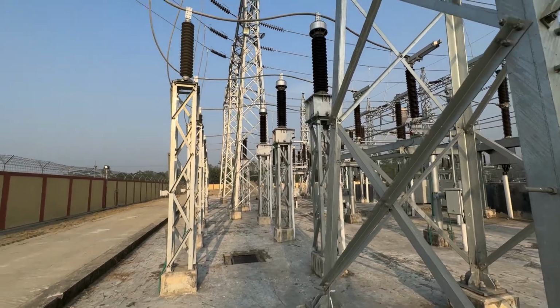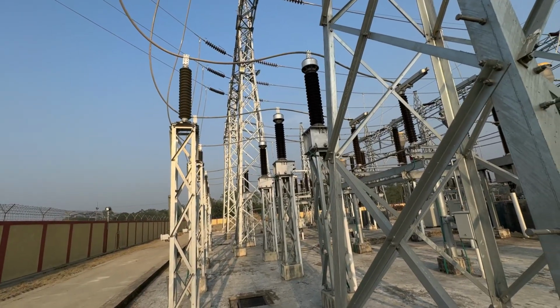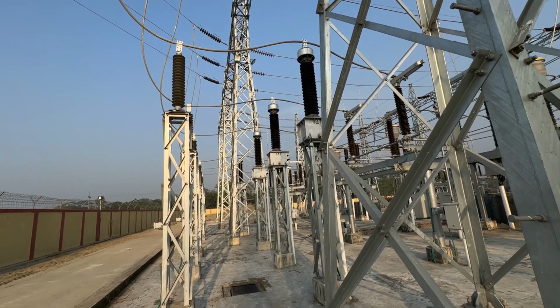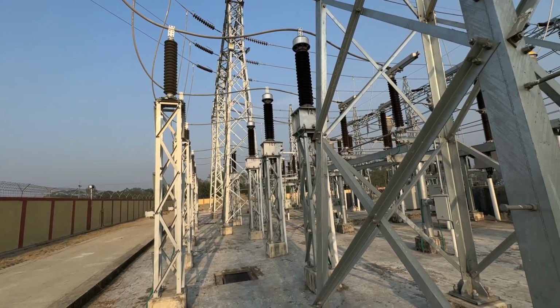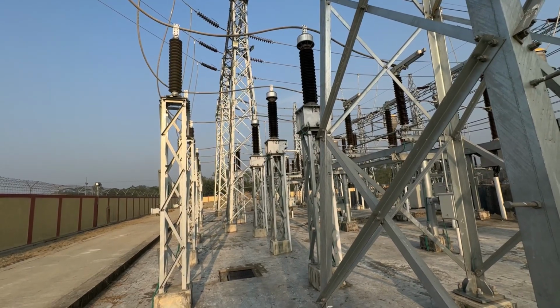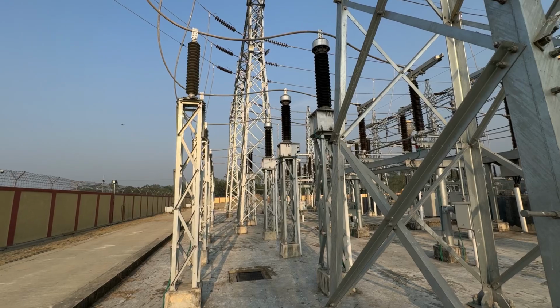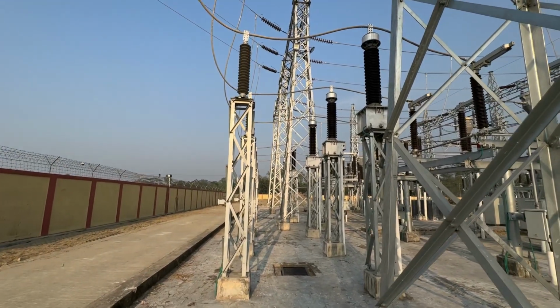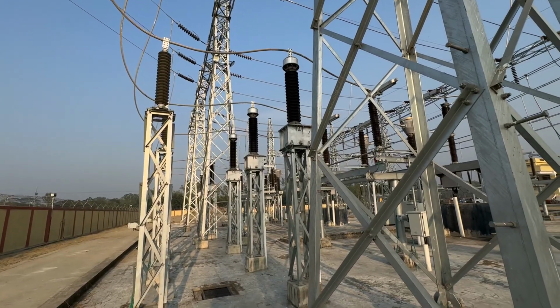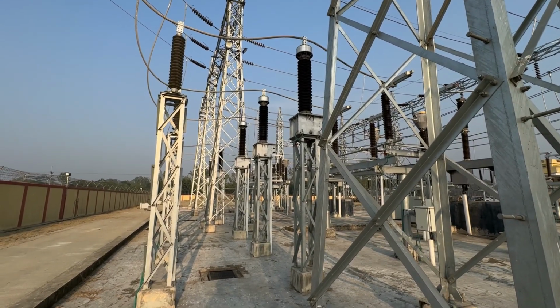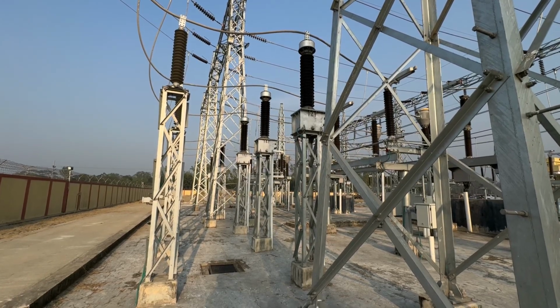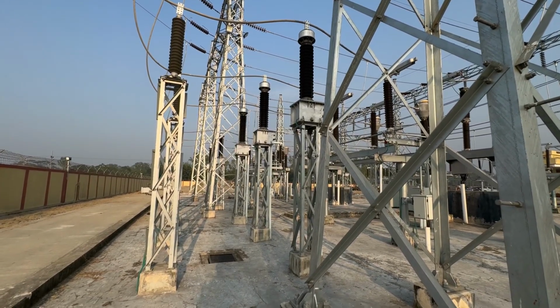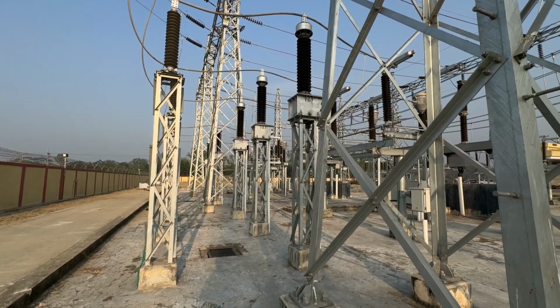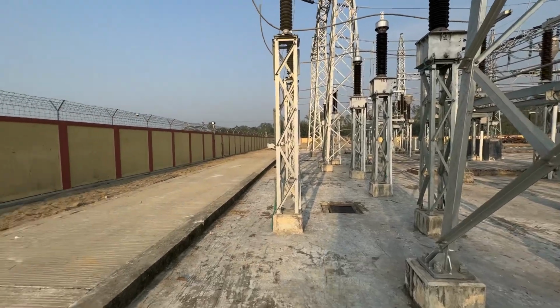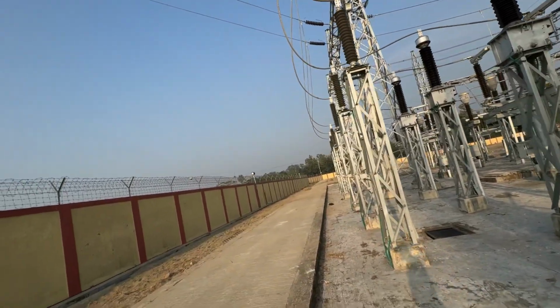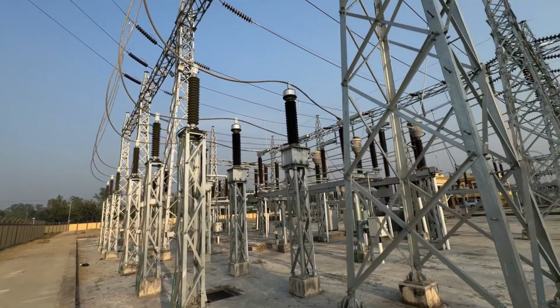A potential transformer steps down the system voltage to 110 volt. It may be 132 kV or 230 kV or 400 kV, no problem, but the output of all CVTs is 110 volt. Then the question is how to step down this voltage, 132 kV to 110 volt. Simply for a PT, it is a primary to secondary step down transformer.